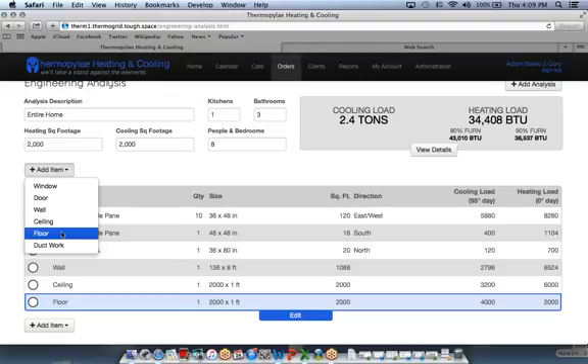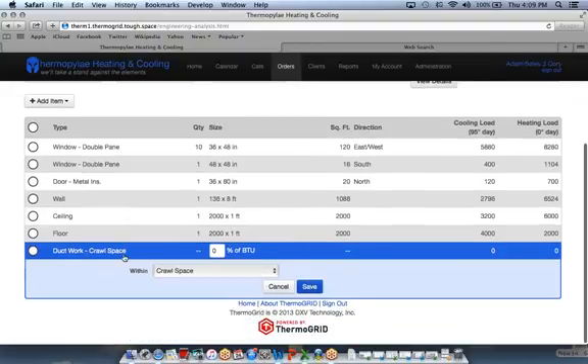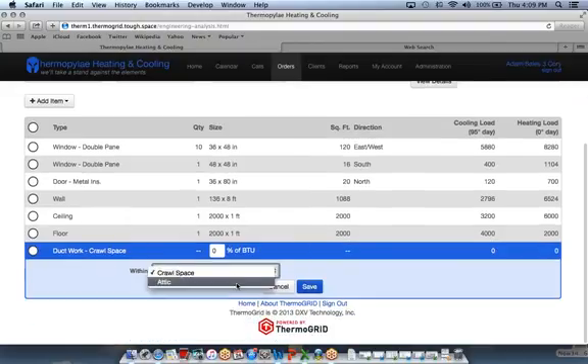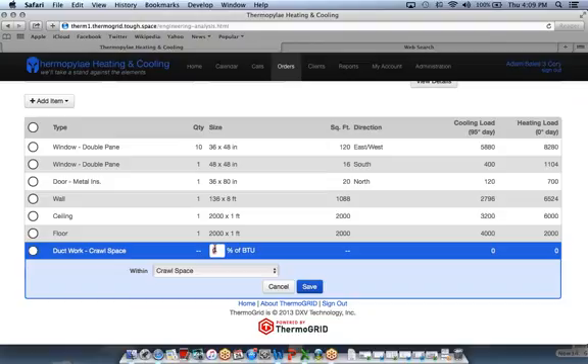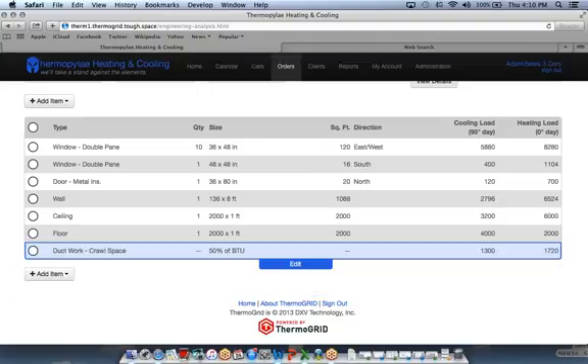If you had a home that had, let's say a crawl space or an attic, and that's where the ductwork was going, you would select ductwork or crawl space. You're going to put the percentage of the ductwork that is going to the crawl space. So if half the home was a crawl space and half the home was over a basement, you would put 50% of the ductwork is going into the crawl space. This particular home, we weren't going into a crawl space, so I'll just go ahead and delete that back out.